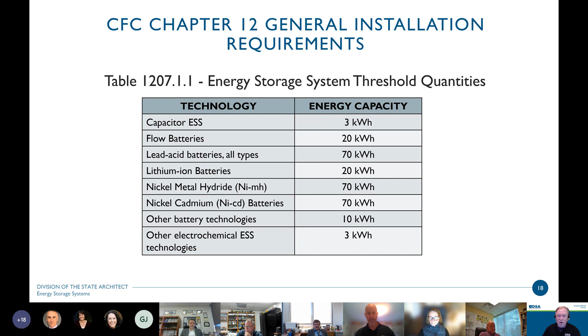And that's how we get into the 1207 requirements. If you're under the thresholds, then no, you're not. But when you look at the thresholds in these tables, they're pretty small. For example, we're talking about capacitor at 3 kilowatt-hours, flow batteries at 20. You can see lead acid at 70, lithium ion, the predominant battery being used right now. We're talking 20 kilowatt hours is the threshold. Anything above 20 kilowatt hours, you have to comply with 1207, and other battery technologies as listed here in the table.